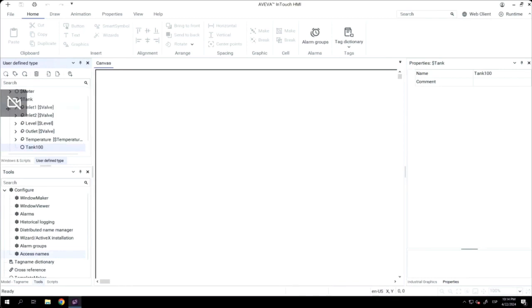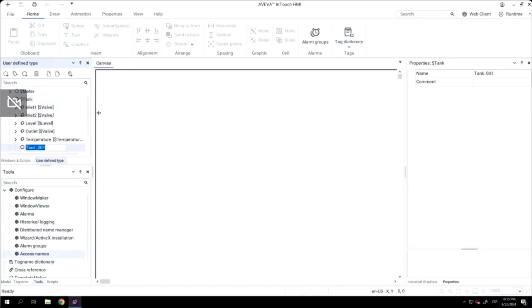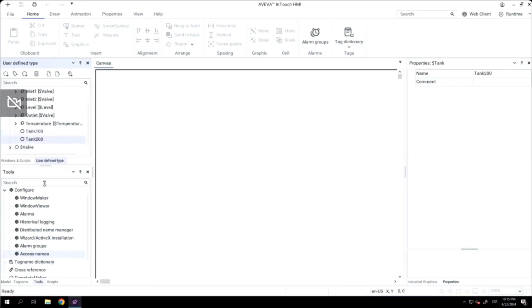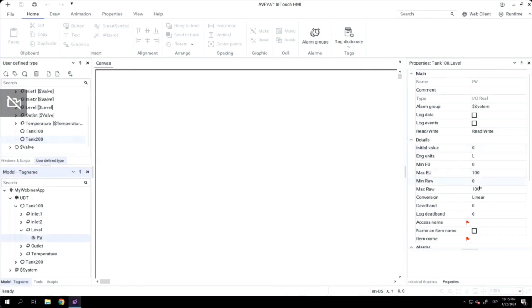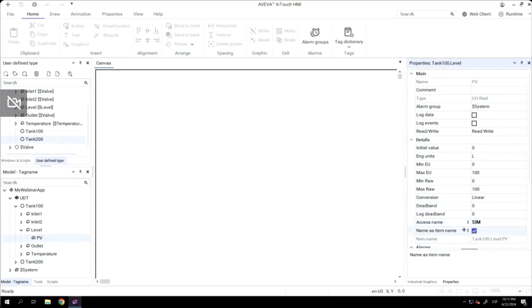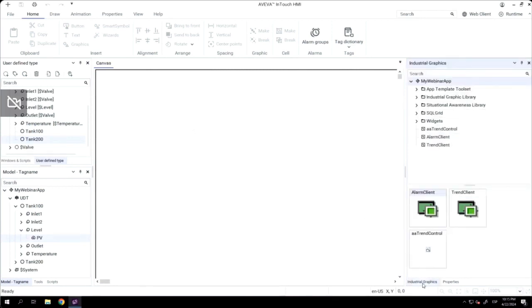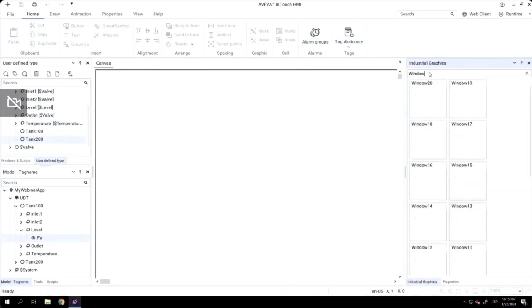Once we have this structure created, it's time to create the instances. Right-click, New Instance, and if we want to modify the parameters of the instance, we should go to the model tag name tab that is here. From here, I can go to any of these components, I can go to any of these members, and then I can modify whatever I need. In that case, I'm configuring or I'm binding this attribute of this member to a real value coming from the field. In that case, it's coming from a simulator.